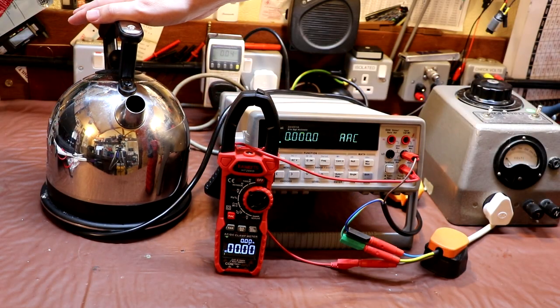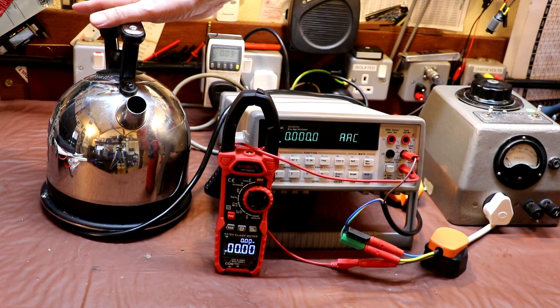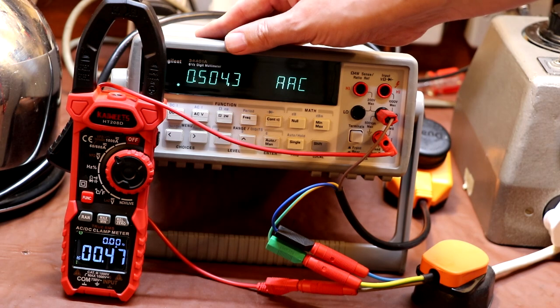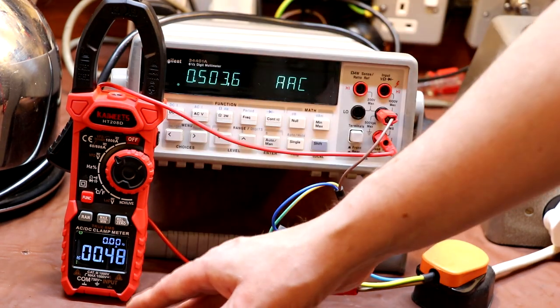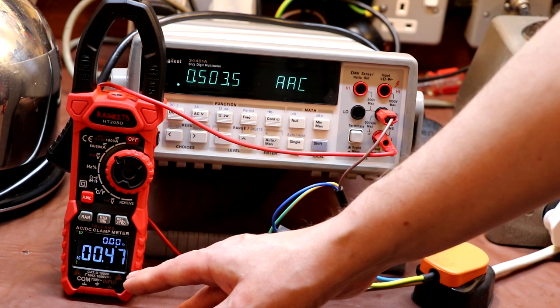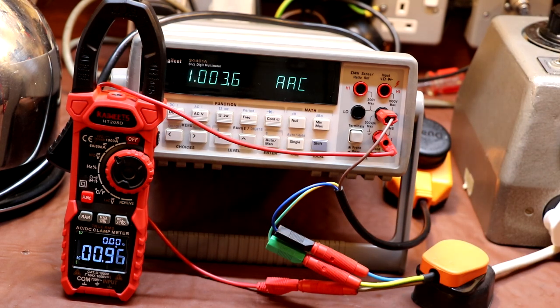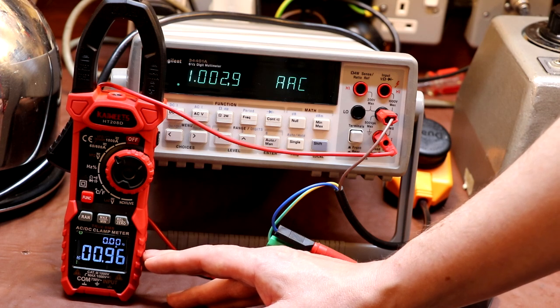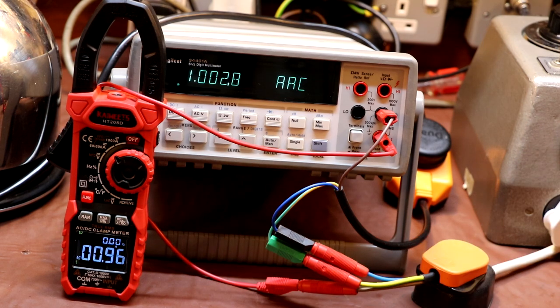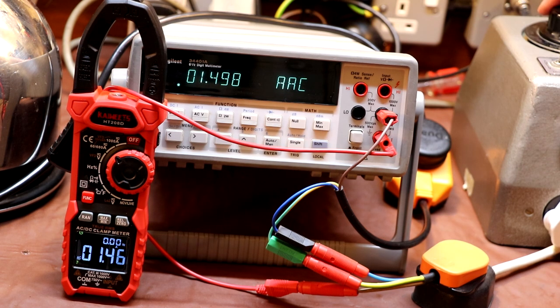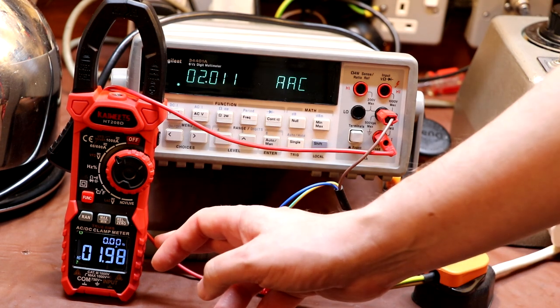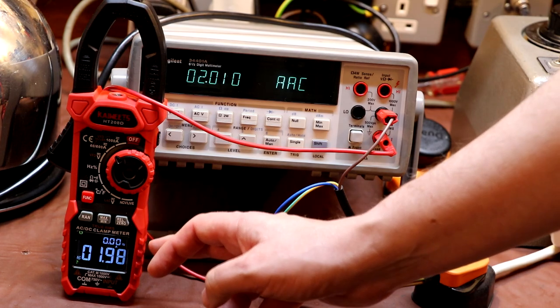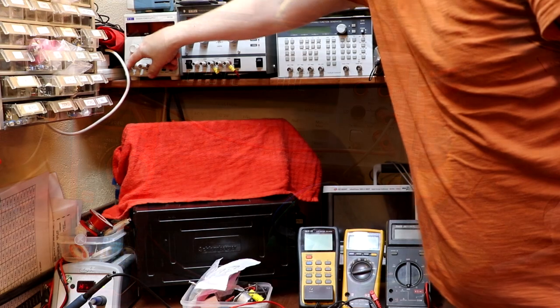As you can see, I'm in trouble because I borrowed the kettle, but kettles full of water make excellent resistive dummy loads, so that's what we're going to use now. We're at just over 500 milliamps now, and our KAIWEETS meter is in fairly close agreement. We're just a couple of counts out at 470 milliamps. At 1 amp we are within specification. We're flicking between 3 and 4 counts out. Now the final current I can set is really limited by the performance of my Variac, so that's going to be 2 amps. So let's go ahead to 2 amps. And at 2 amps, occasionally the KAIWEETS meter is 1 count out, but really they are in close agreement now.